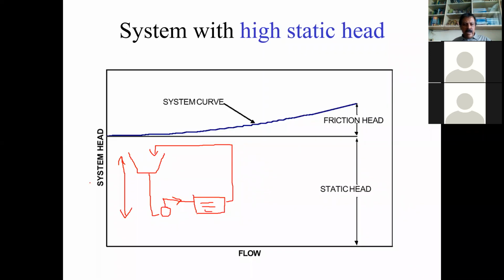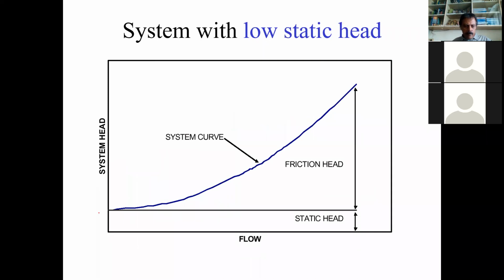In this case, the static head is very high and the frictional head is very less. There could be other cases, and most of the time it will be a little bit of static head and a large amount of frictional head. This is a typical industrial situation you will come across. Now, whatever we have seen so far is in relation to the system. This is called the system curve. The system curve has nothing to do with the pump. It is a curve which shows how your system will behave if you put in different quantities of liquid.